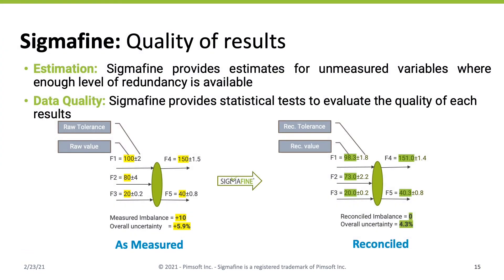Let's look at data quality. Here we have five flows — three going in and two going out — and an imbalance of 10, with an uncertainty of 5.9% on this simple system. Looking at the reconciled data set, the uncertainty has been reduced to 4.3% and the imbalance has been eliminated. For example, flow two had an uncertainty of 4 on 80, which is 5%, and that uncertainty has been reduced to 2.2 on 73 — a 40% reduction in uncertainty without changing the technology of the instrument. This is the power of data reconciliation.